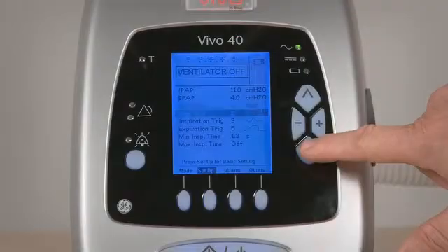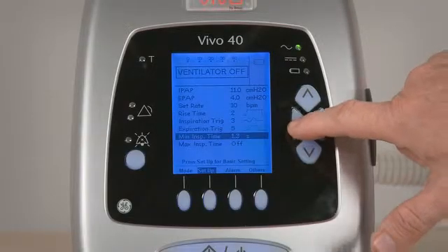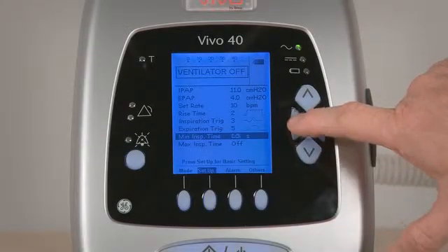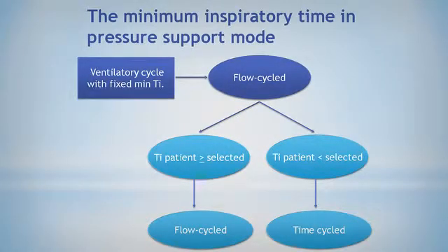Another important feature of the Vivo40 ventilator is the possibility to set in the pressure support mode a preselected minimal and maximal inspiratory time. When selecting a minimal inspiratory time, the algorithm of the ventilator operates as follows: if the inspiratory time of the patient's breath is longer than the minimum inspiratory time selected in the ventilator, breaths are flow cycled.